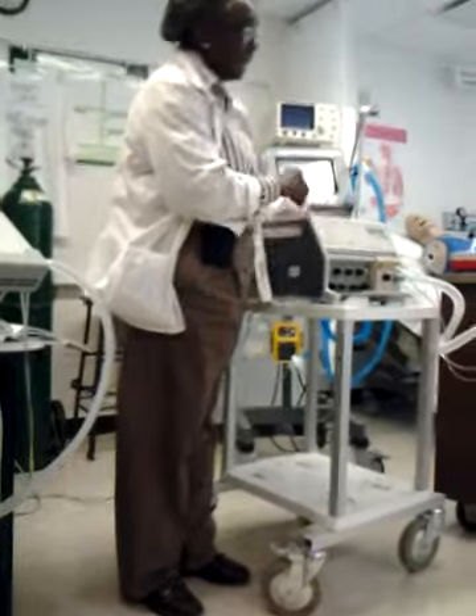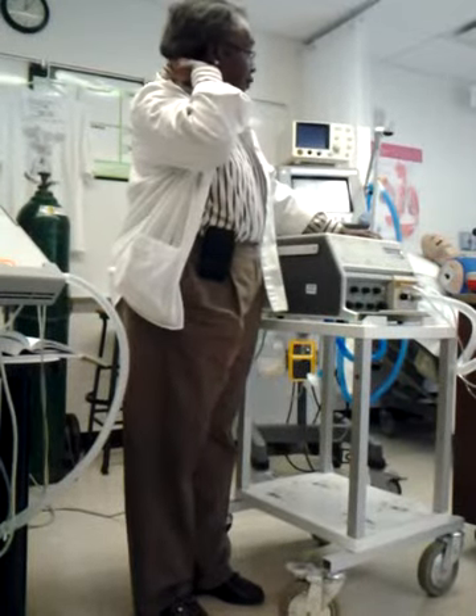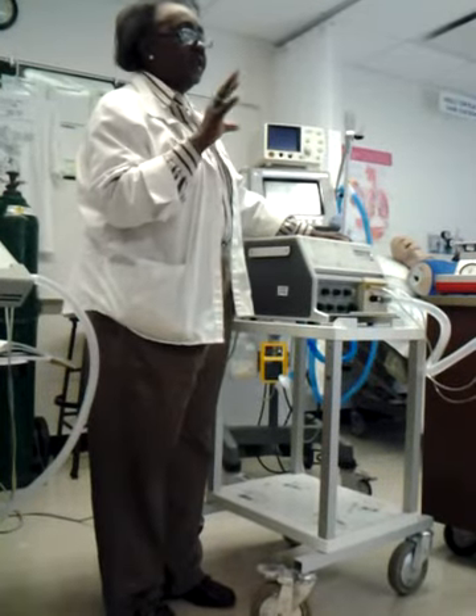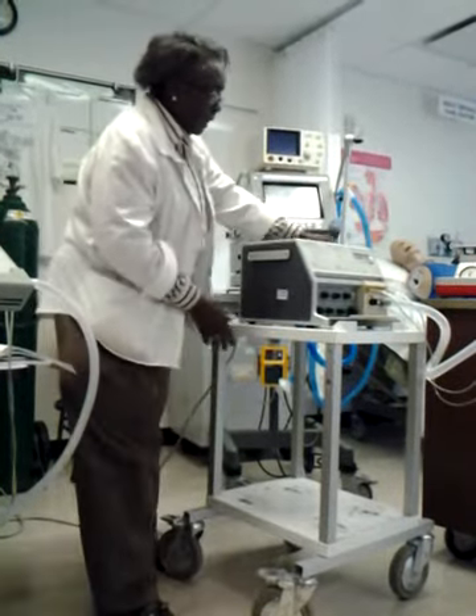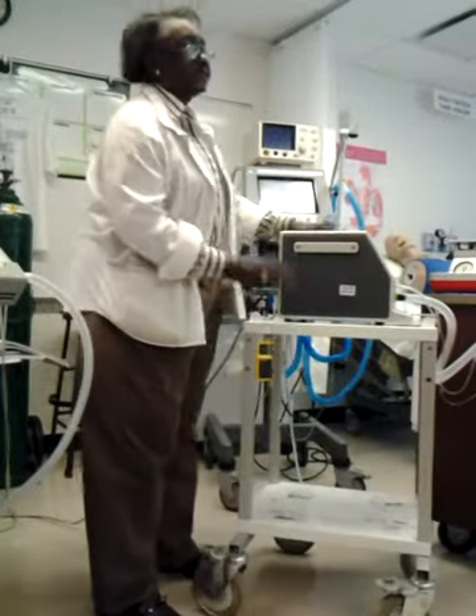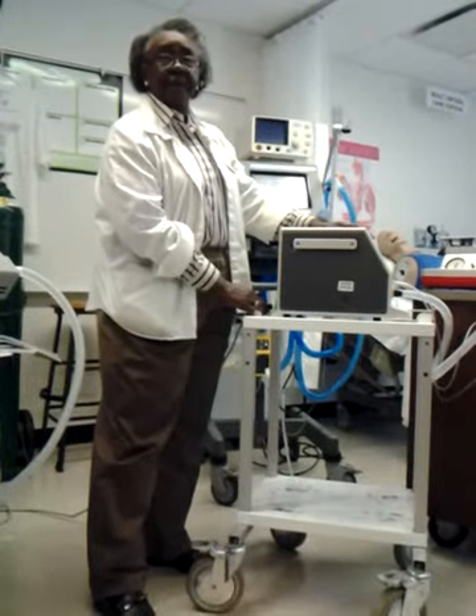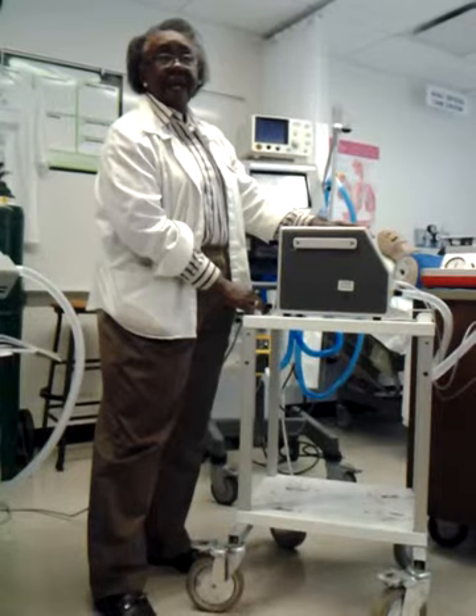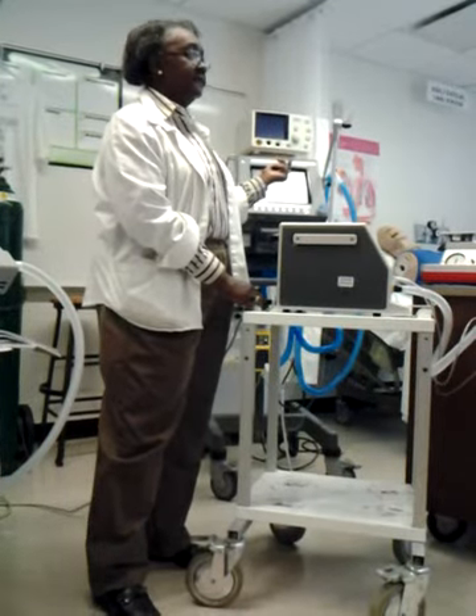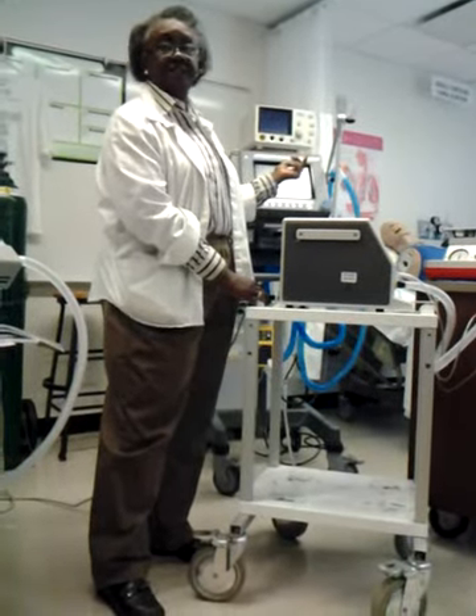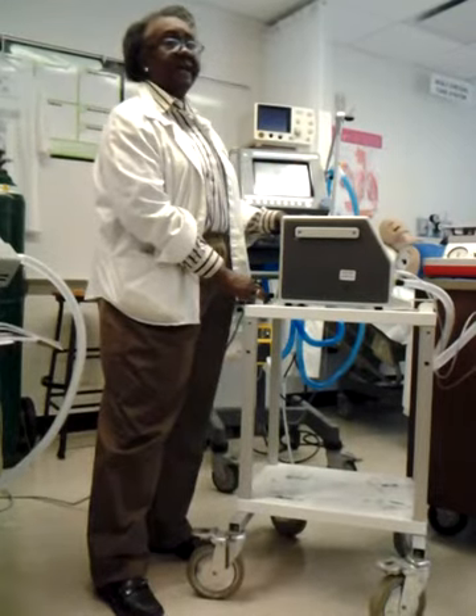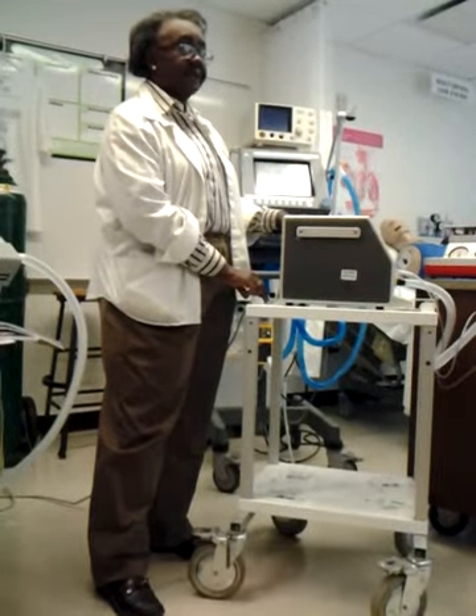The LP10 is one of the more commonly used ones. Actually, this is an older version, but I find that it's very commonly used still. There are a lot of home care ventilators out there. They're coming up with new ones every day. Home care ventilators, of course, are electronically powered. In order for them to be pneumatically powered, you would have to have some kind of 50 psi gas source in the patient's home, which in most cases you will not have, so you want them to be electronically powered.